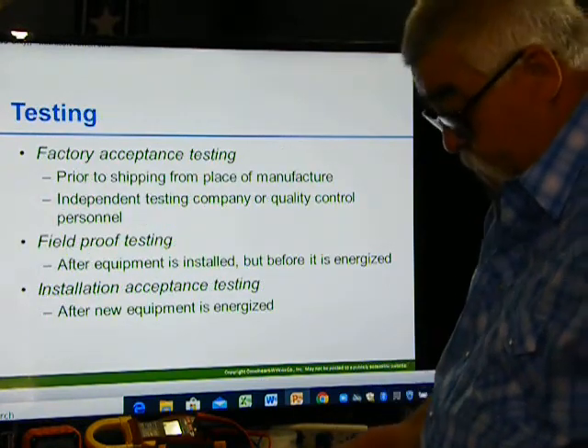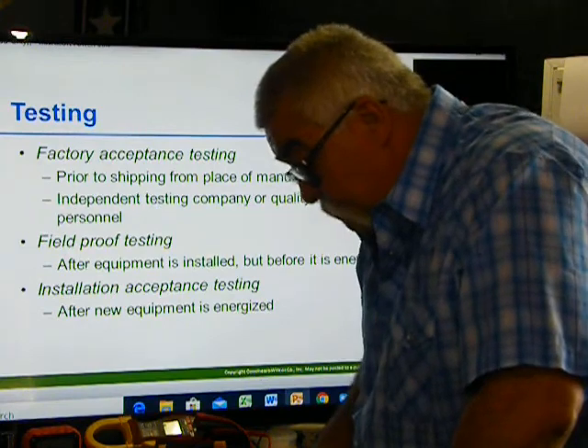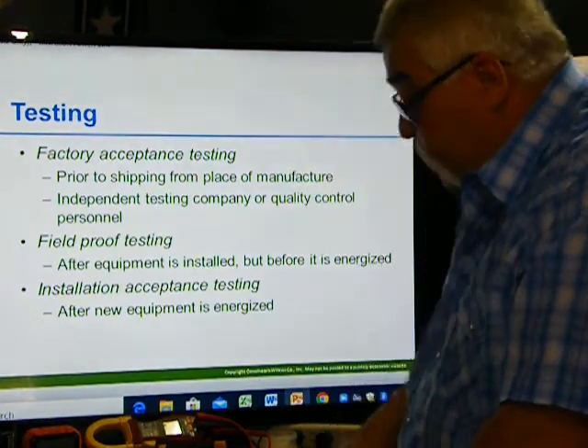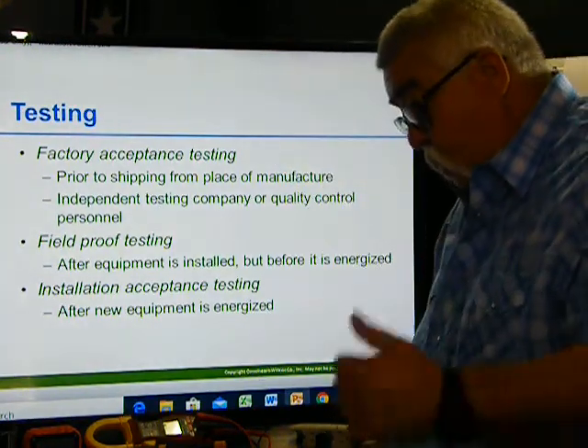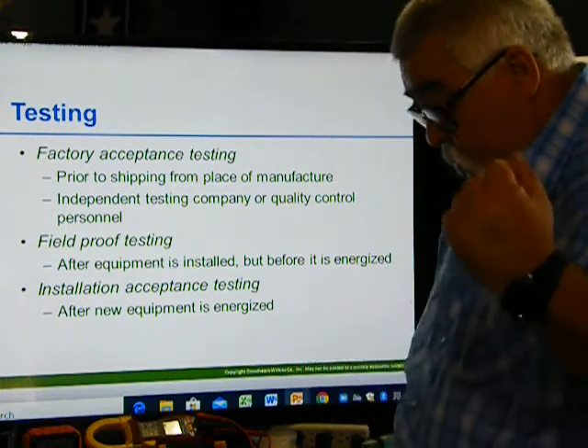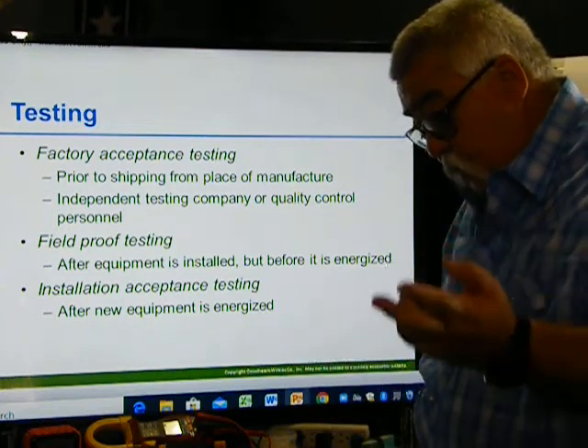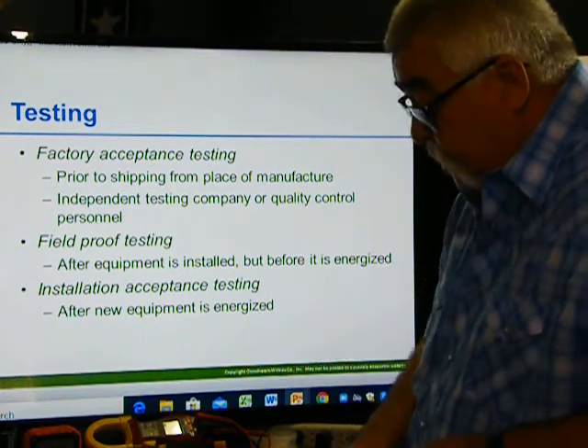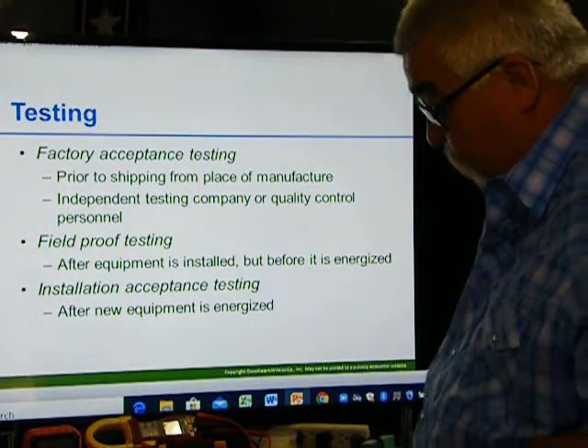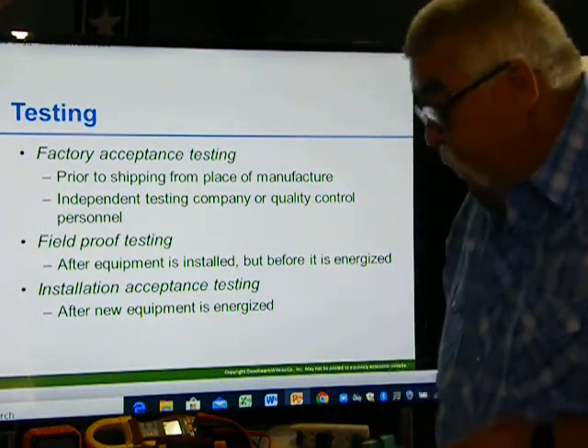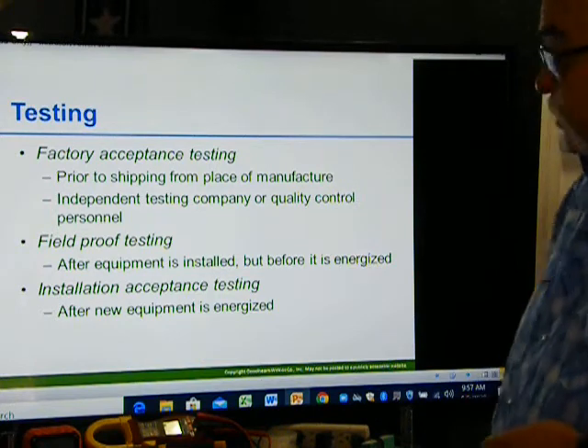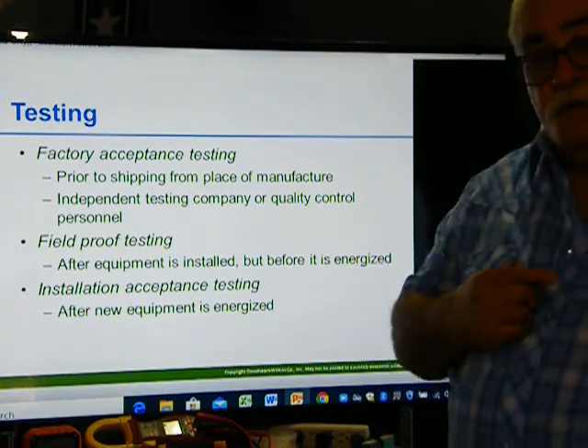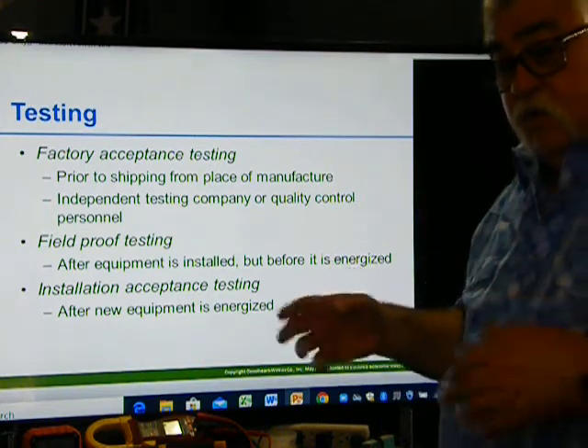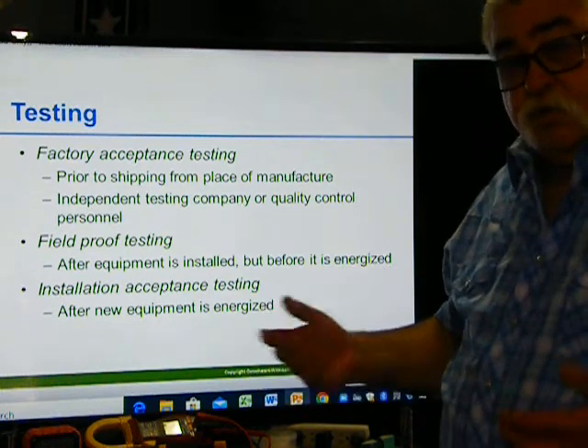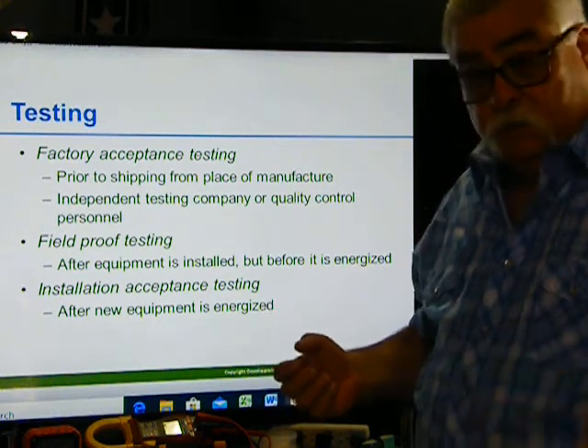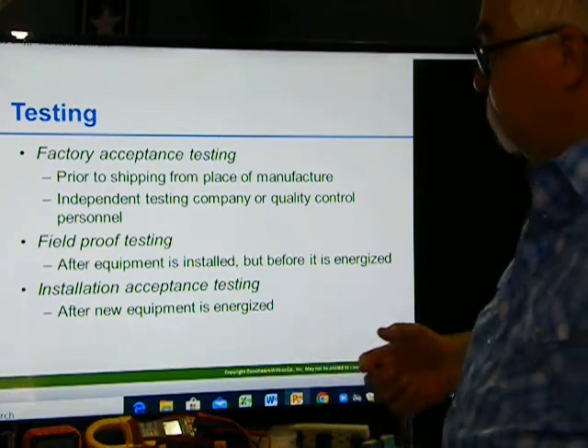Testing. There's 5 broad categories for testing in the electrical equipment. We have factory accepted testing, field proof testing, installation accepted testing, planned maintenance testing, and troubleshooting. Okay, for the factory accepted testing, that's done at the factory. So the factory makes this, and then their engineers get there and they check it to make sure it's going to work according to specifications that it was designed for.